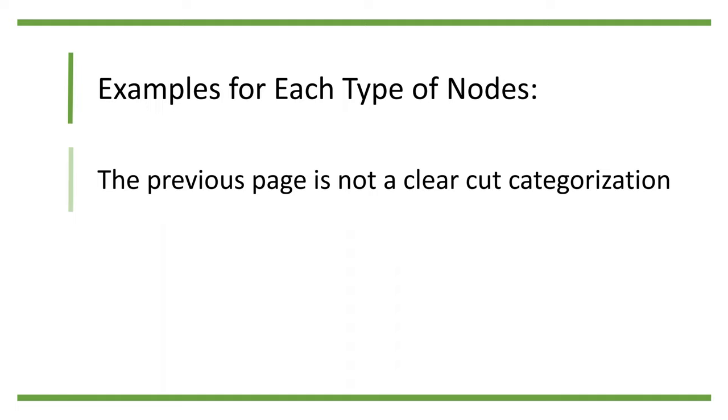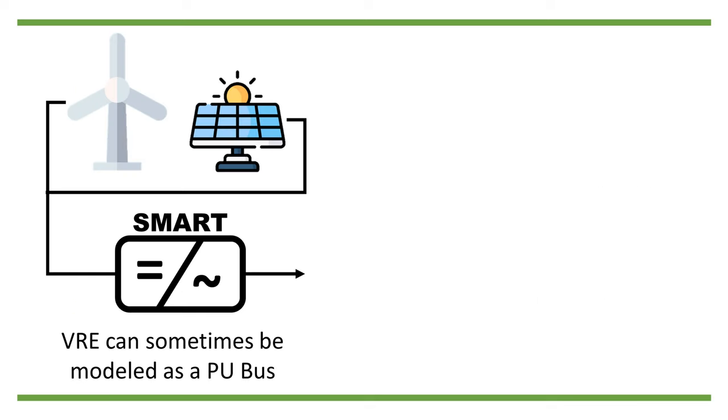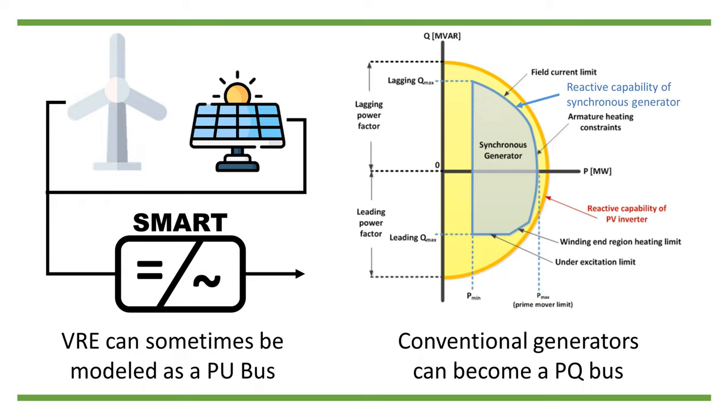Please note that the purpose of this chart is not to provide a clear-cut categorization. The type of bus of a node depends on the controllability of the devices connected on the node. For example, VRE with grid support inverters can be viewed as a PU bus to some extent. Meanwhile, when a conventional generator reaches its reactive power limit, it can turn into a PQ bus.